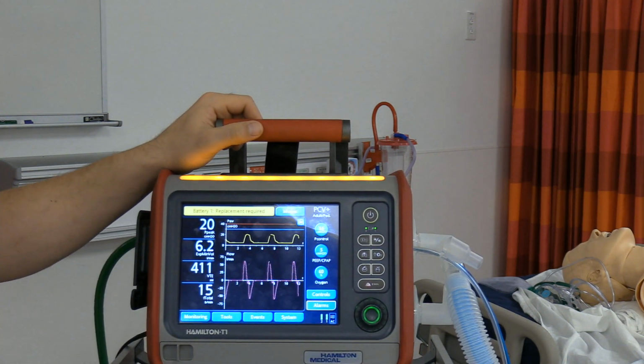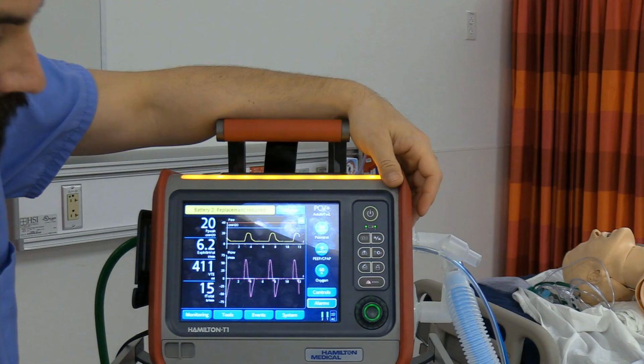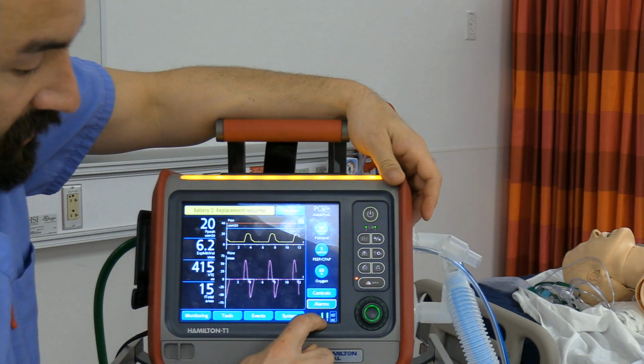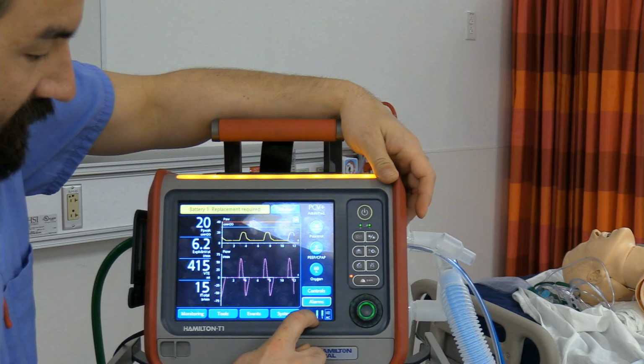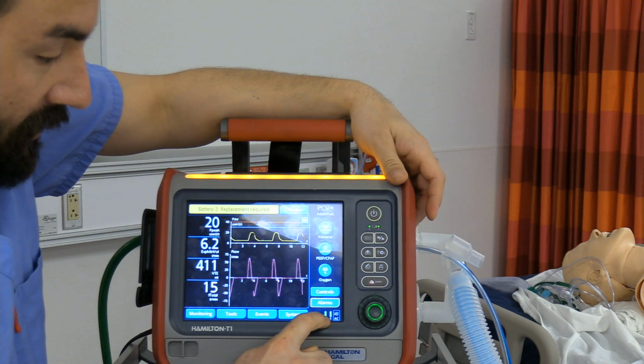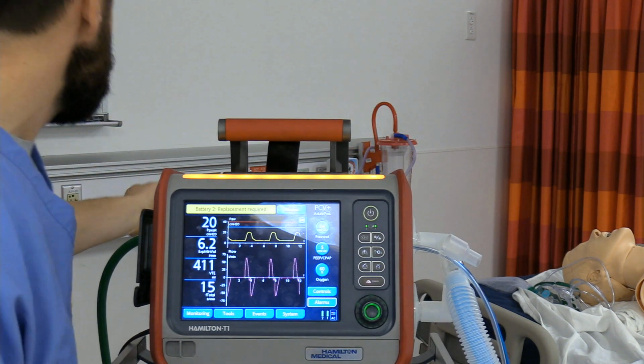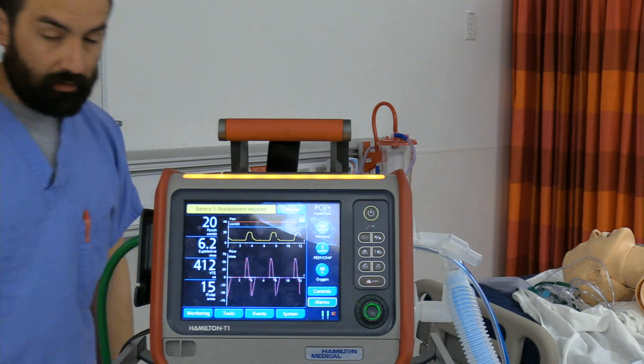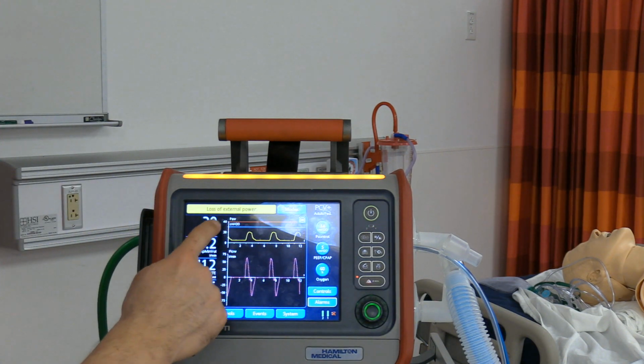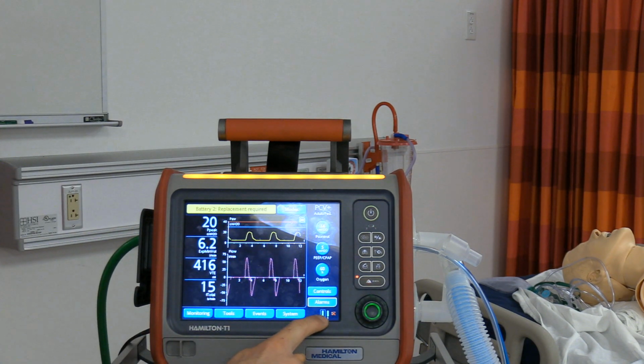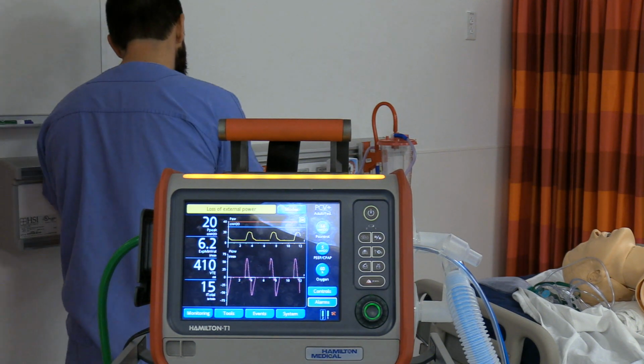So, a couple other things here. We're not going to talk about alarms. It's showing that both my batteries are charged. I don't know why it's giving me the requirement there. You can see batteries, and I'm on AC power. If I disconnect from the wall, it's going to tell me loss of external power. I get an X right there, and it's showing me that I'm running on one of my batteries. Both my batteries are green. These things have a pretty good long battery life. Plug back in.